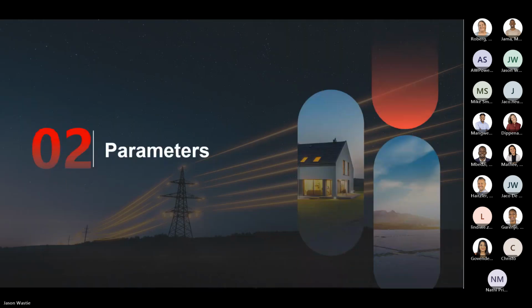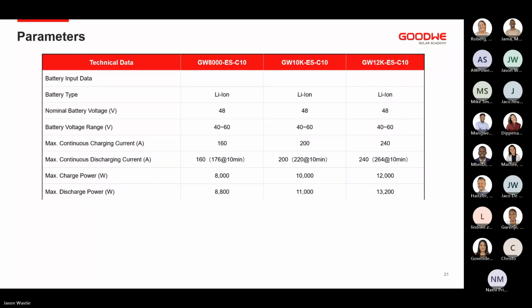So let's have a look at some of the parameters of the ES Unique. So we have got three models, the 8, 10, and 12 kilowatts. For the battery input data, it is compatible with the lithium-ion batteries. Obviously, it's a low voltage inverter, so you'd need batteries within the range of 40 to 60 volts. The max charging current is from 160 to 240 amps, depending on the inverter.